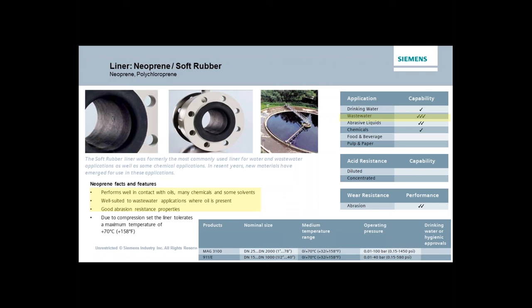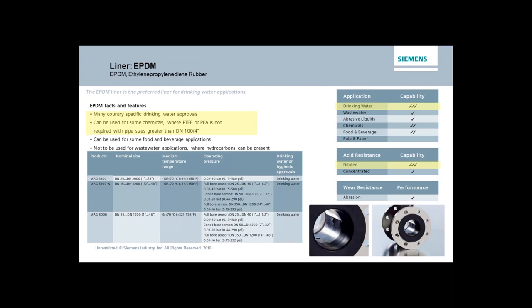PFA is basically a type of Teflon. It is used in food applications pretty regularly and also in industrial applications because of its chemical resistivity. The reason we use it in food is because it doesn't leach, so there's no worry about any material contaminating food processing products. It has a good temperature range, meaning it can be steam cleaned even at high temperatures of 300 degrees Fahrenheit, making it a very flexible solution from both ruggedness and application standpoints.